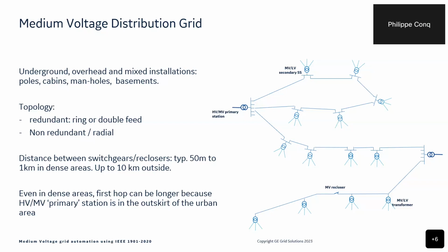About dense areas, even though the typical distance is limited to maybe less than 1 kilometer, very often the very first hop between the primary station and the first secondary substation is pretty long. So you don't want to live in the neighborhood of a primary station - it's a big yard with HV lines, not very friendly.